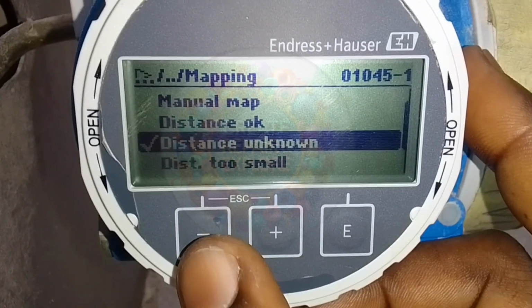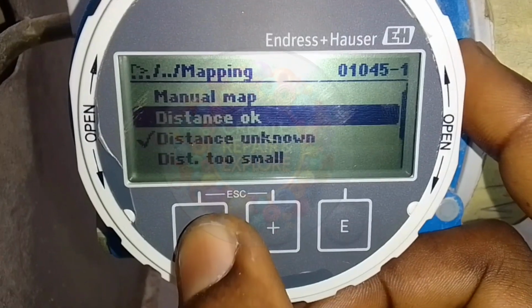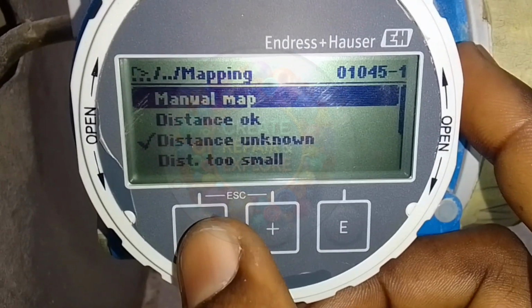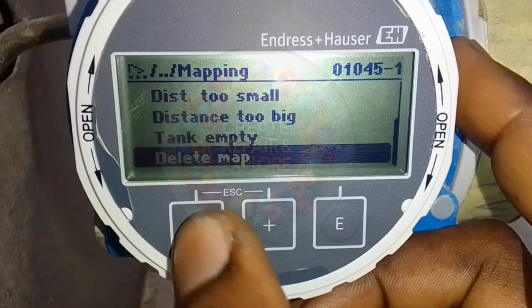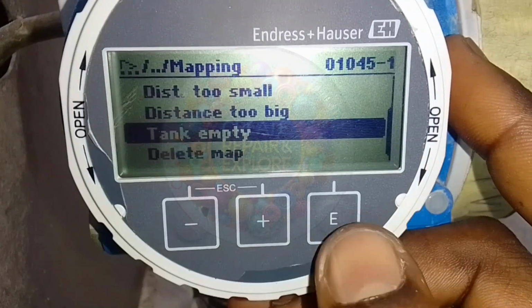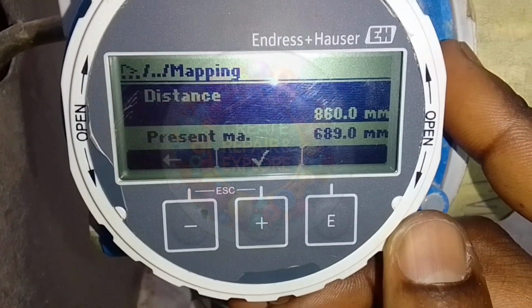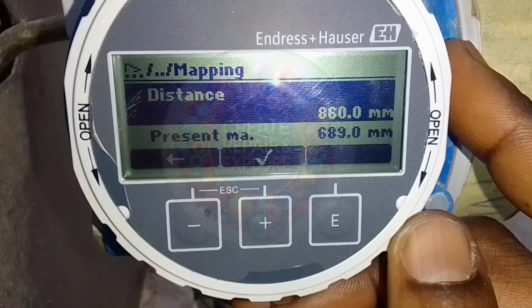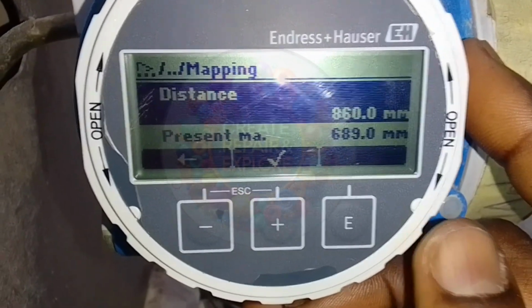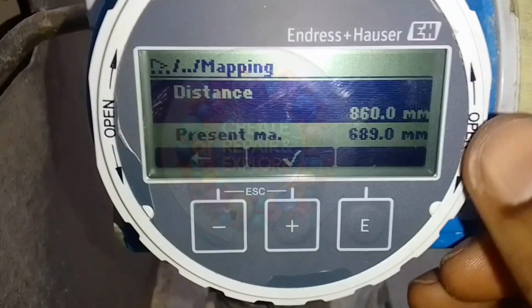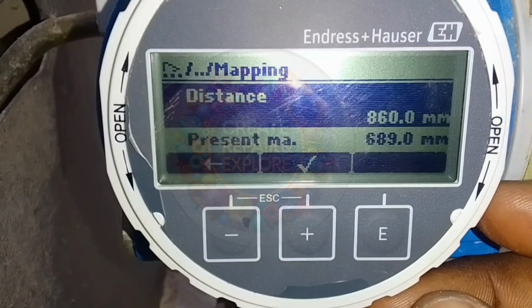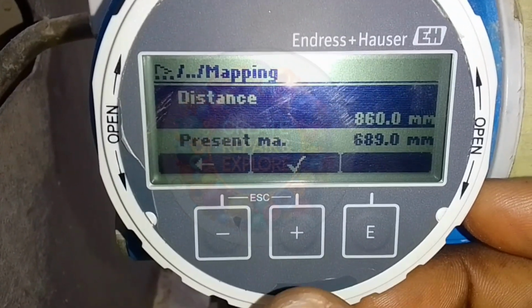Then use the plus or minus key to scroll to tank empty. Press the enter key to select tank empty. The calibration will take just a few seconds, and then you will see the distance turning to the full length of the probe. To confirm this length, check the data information on the body of the probe.